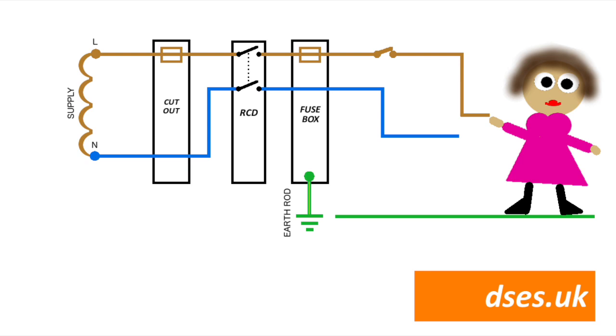Now my picture here is a little simplistic when it comes to RCDs and earth rods as you'd normally have a time delayed RCD for fault protection on a rod with a 30mA RCD for additional protection on the final circuit. But that may be for another day and the picture illustrates the general point.